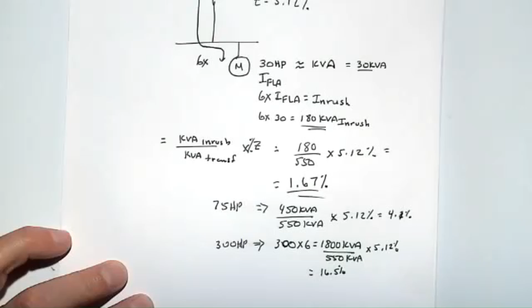And then looking at it for a 300 horsepower motor, we have 300 times 6 times inrush to give us 1800 kVA divided by 550. So again, that number is going to be bigger than the impedance. In fact, it's 16.5%. Now, what's interesting about this is our inrush kVA, our 1800 kVA, is actually bigger than the transformer by a good bit, more than 3 times. So we're seeing about 16.5% voltage drop. What's going to happen is we are going to see a significant notice on light flicker, but we may also have equipment dropout.